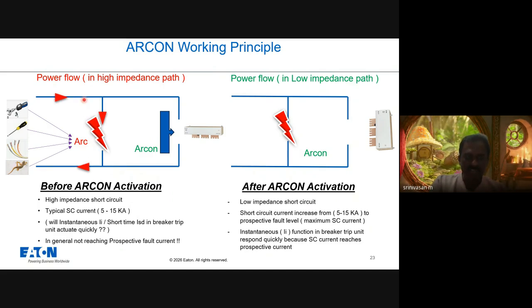The internal arc is nothing but, as I said earlier, a high impedance short circuit. In the majority of cases, the internal arc value will be between 5 to 15 kA. Even if you have an ACB with instantaneous short circuit protection, the time required by the instantaneous protection to clear the fault will be longer.